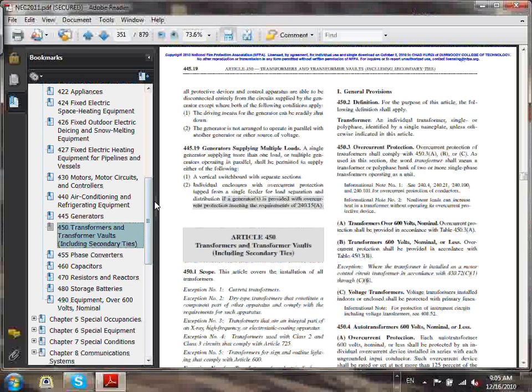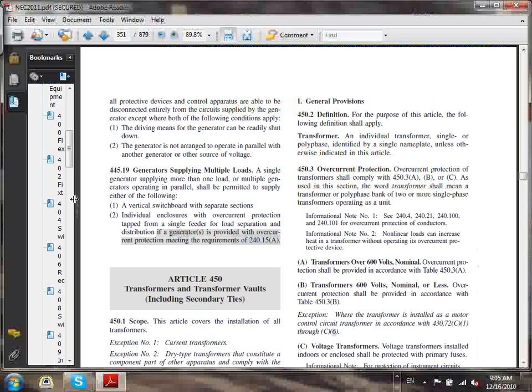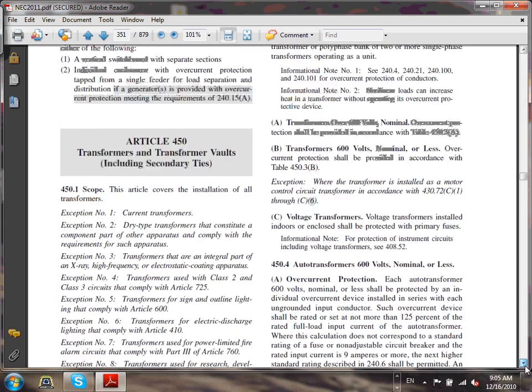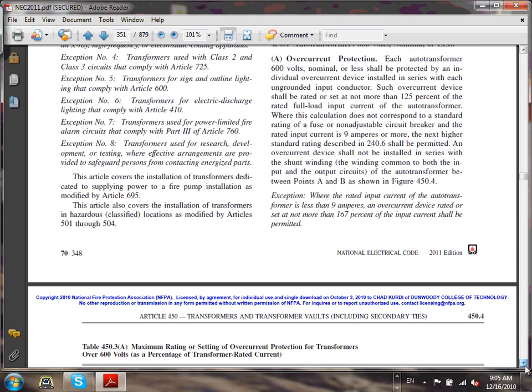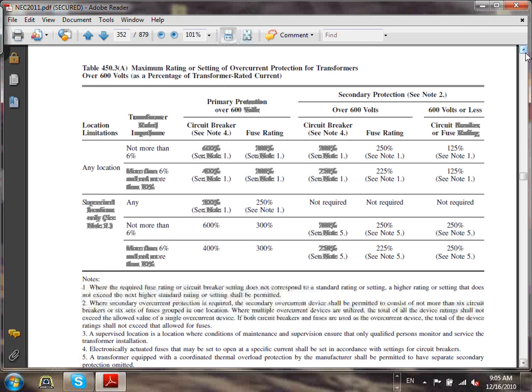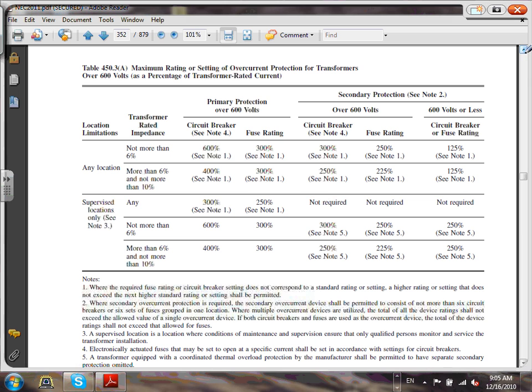Here's my 450. Just to highlight a few things here, Article 450. I'm looking at 2011, guys, it's the same way. Okay, here's a table that I want you guys to use. Make sure that you know how to use it. You're looking at the maximum rating or setting of overcurrent protection device for transformers over 600 volt. Did you guys hear that one? Over 600 volt, meaning the primary or the secondary are over 600 volt.